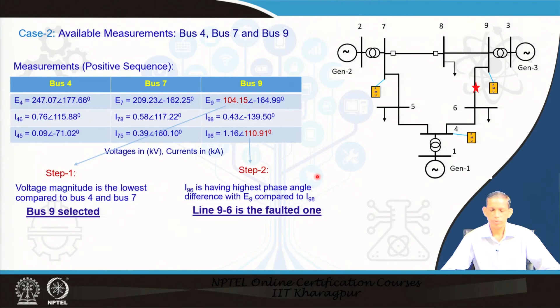How? Now, what you see is this 9 bus system, and we have PMUs. We collect data at a control center, and this control center can process the corresponding PMU data, align them in terms of time alignment, and then it can be used. So, we have these 3 PMUs and then we identify the faulted line at the PDC and the controller level. Once we calculate that, we check whether the fault is in zone 3 of any relay, at the central level. If yes, then the corresponding relay should remain active; otherwise it should be blocked.